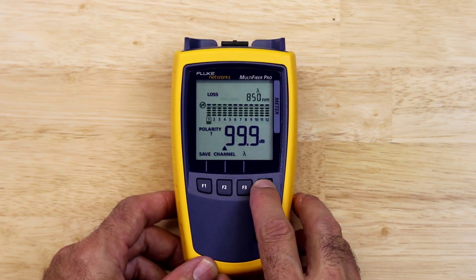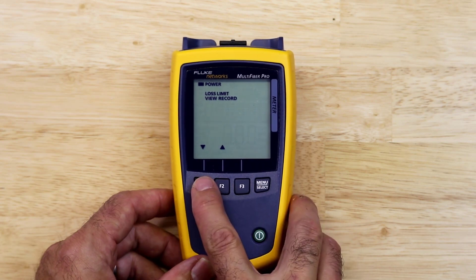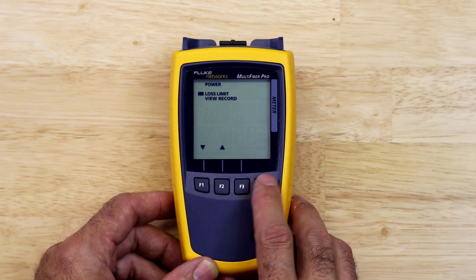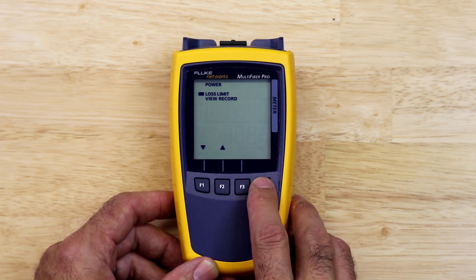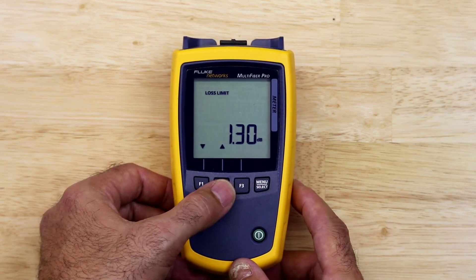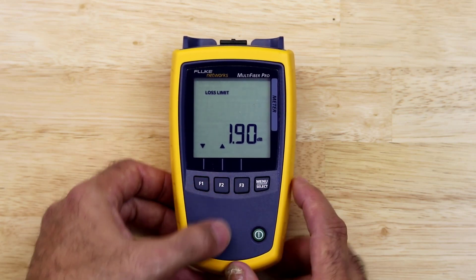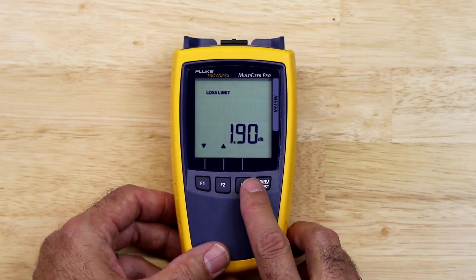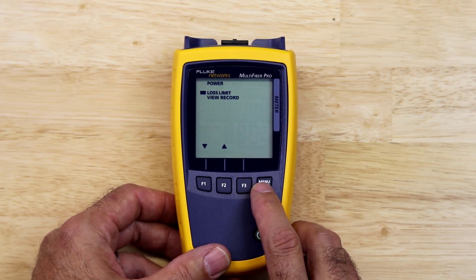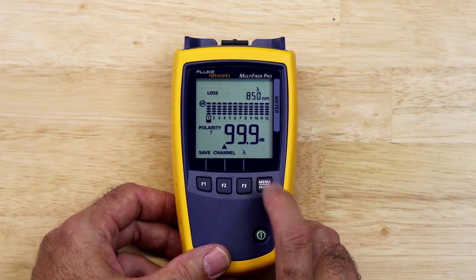I'm going to press the Menu Select button for 3 seconds. That will bring up a menu where I can enter the loss limit. I will hit the F1 key once to go to the loss limit. Then I'll press the Menu Select to go to the loss limit screen. Now I'll use the F1 and F2 buttons to change the loss limit to the value I looked up in the limit lines. In this case, I'll set it to 1.9 dB. I'll press the Menu Select to save the limit. I'll then press the Menu Select for 3 seconds to go back to the main screen.